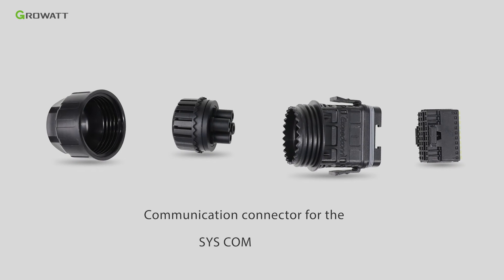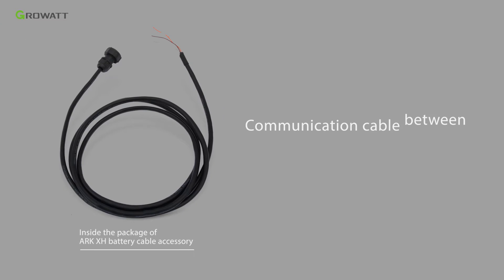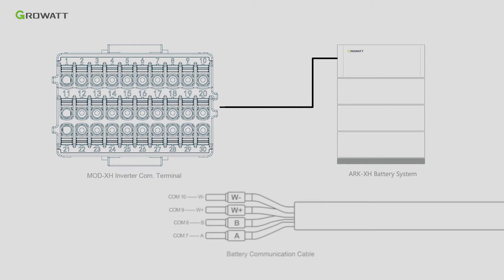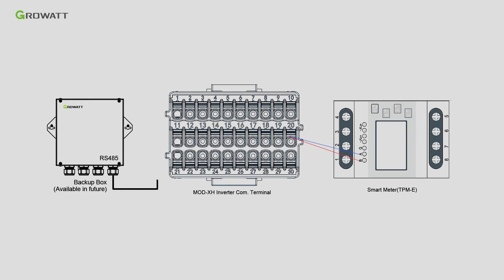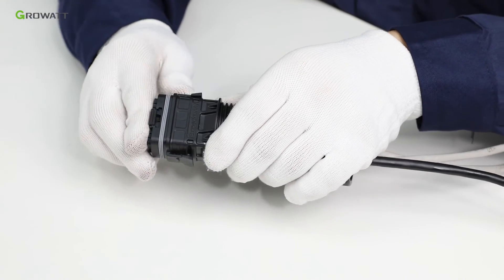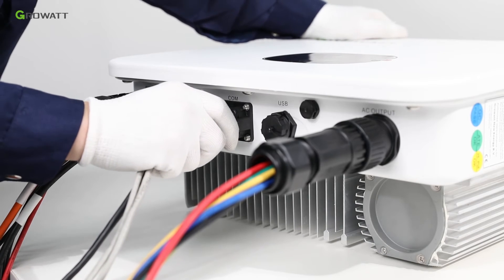Here is the communication connector for the COM port. The definition of each port is shown in the table. The communication cable between the MOD-XH inverter and ARK-XH battery is provided by GROWATT. Follow the number label to connect the communication connector. Connect the communication cable from the smart meter and backup box to the communication connector. Thread cables through pressure screw, C-ring, and threaded sleeve in sequence. Remove the cover from the terminal and connect the communication connector to the COM port of the MOD-XH inverter.